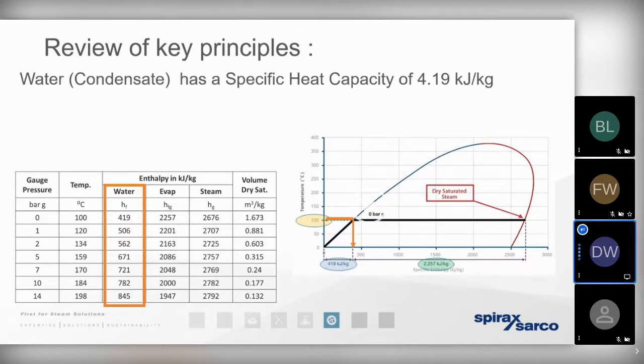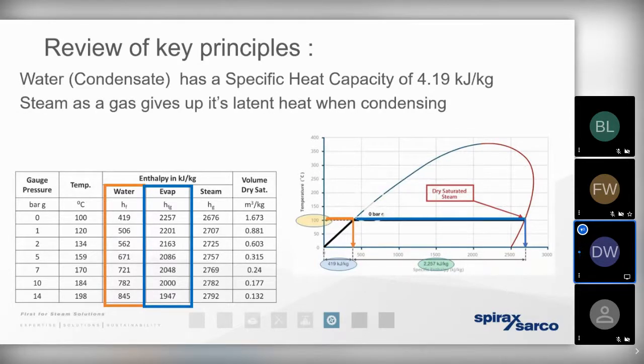In order to turn that boiling water into steam, it needs to evaporate. So we then add what we refer to as the enthalpy of evaporation. That's the energy that's demonstrated in the box in blue on the screen that you can see. So for example, at zero bar gauge, when we've added 2,257 kilojoules of energy to a kilogram of water at boiling point containing 419 kilojoules of energy, that's when that kilogram of water will fully change state, evaporate, and produce a kilogram of steam.